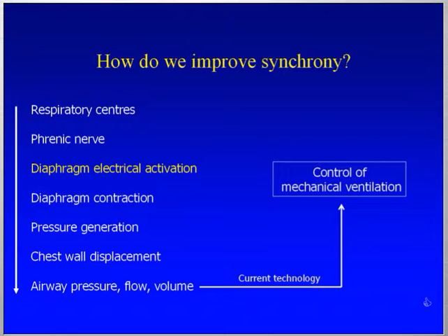It is these signals, these pneumatic signals, that are today used to control the mechanical ventilator. However, you can imagine that, especially in disease, the original signal from the respiratory centers can be filtered, delayed, dampened, and transformed by the time it gets down through the whole chain of events.